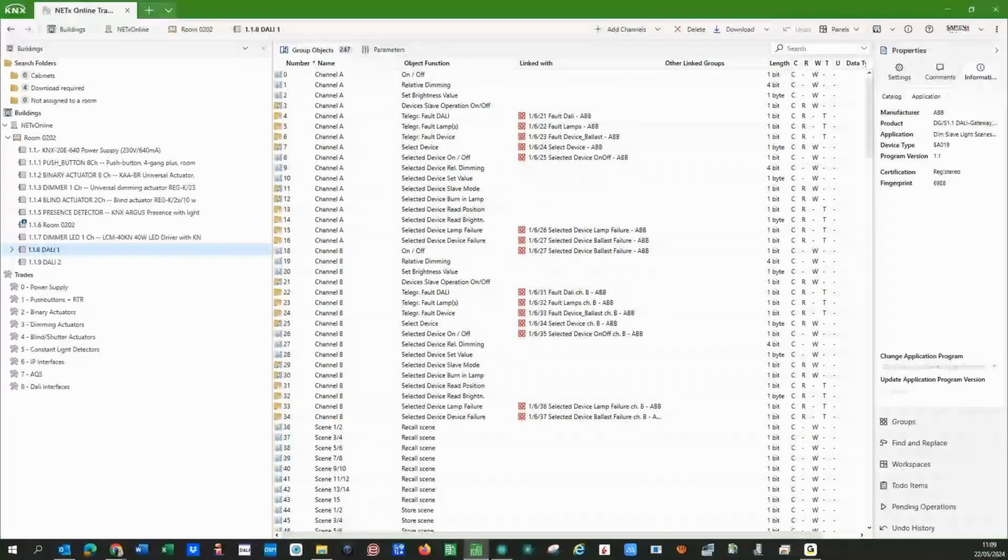What we do with the LaMPS module is to resume this polling to the lamps and the ballasts, this checking of the status of the lamps and the ballasts, by gateway. So we do not need to open the parameters and activate all these objects for each ballast, for each group, because we can do it in a centralized way per gateway. To do this, we just have to follow instructions coming from our web manager.